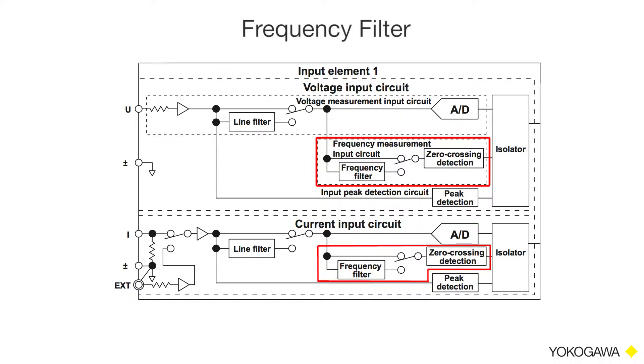This is also a key advantage of using a power analyzer instead of an oscilloscope to make power measurements. The frequency filter acts as a filter for detecting the zero crossing of the synchronization source more accurately.